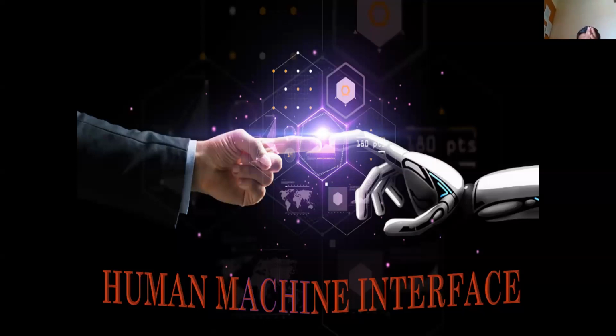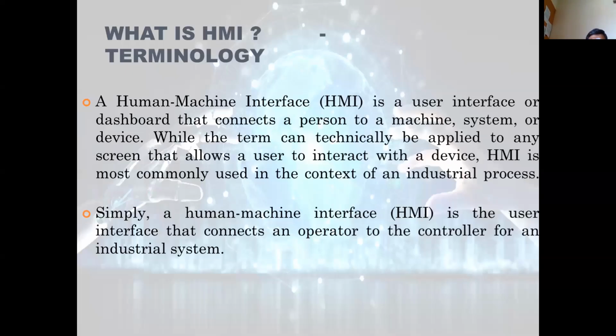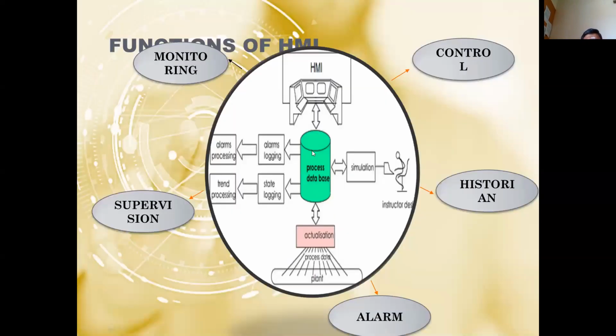So there is no major difference. The only difference is the HMI will control only a part of the unit of the plant, whereas SCADA supervises all parts of the plant. The HMI's data will go into the SCADA, so it can be used for monitoring and supervising alarms. Alarms are important for industries. If any fault happens, an alarm will occur and alert the process and technical persons.